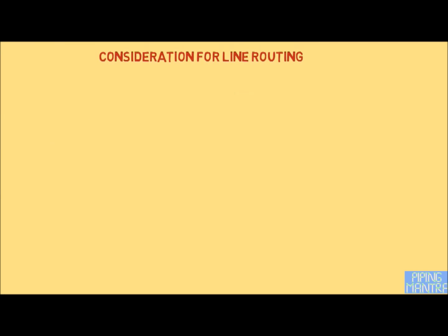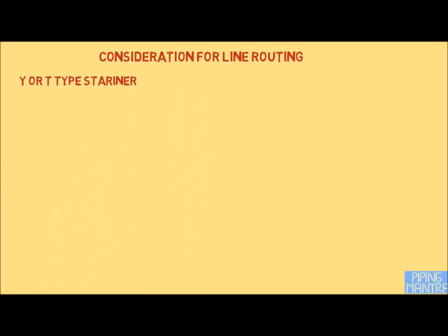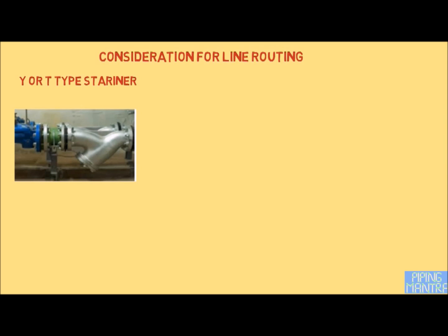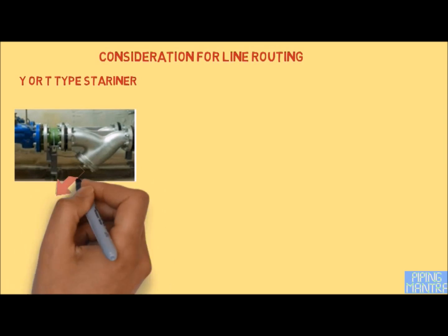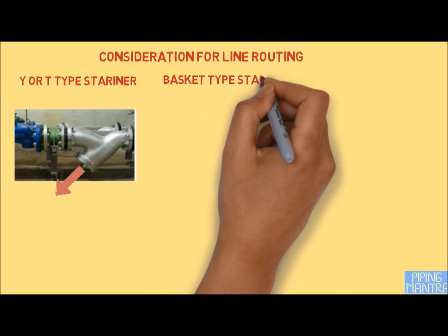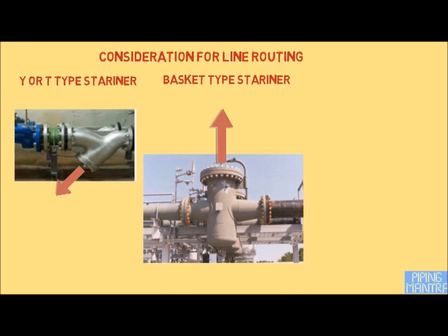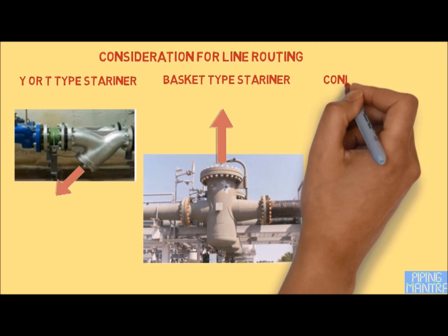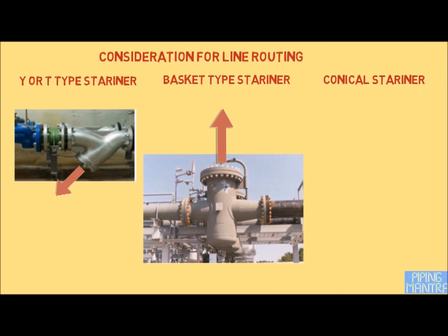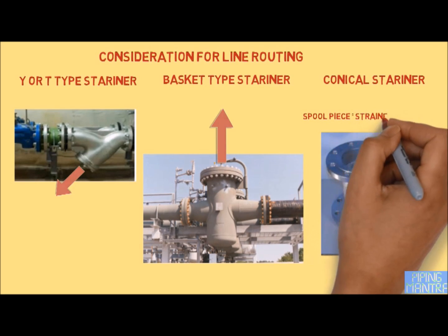Piping should be arranged to provide sufficient clearance around equipment such as pumps, turbines, compressors, agitators, and heat exchangers for maintenance purposes. For strainers, adequate clearance is also required: for a Y-type strainer, the strainer screen is removed from the bottom so clearance is needed below; for a basket-type strainer, the screen is removed from the top so sufficient space is needed at the top. For a conical strainer, a spool piece with length at least equal to the conical strainer length is required for installation in the pipeline.